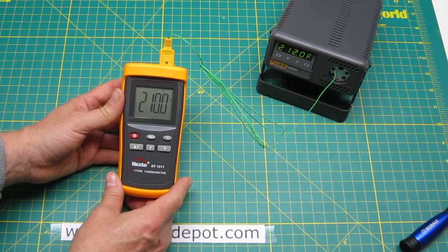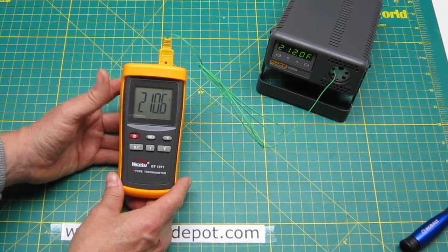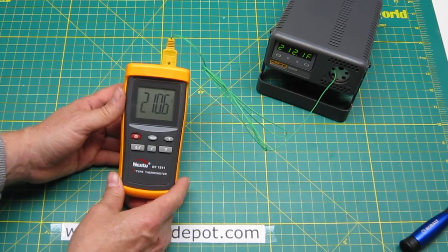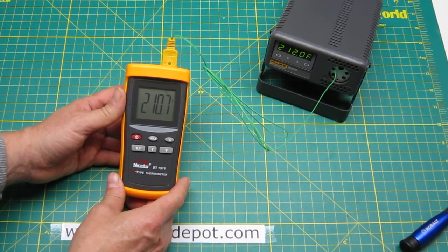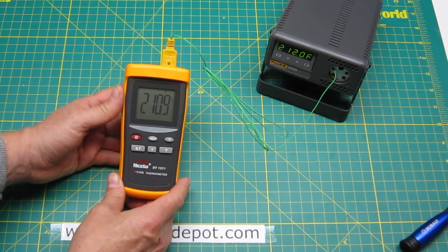Also you should keep in mind that thermocouples age. So after a few years, especially if you're using them in a kiln or high temperature application, you should exchange them because they have aged and changed and give not an accurate signal anymore.